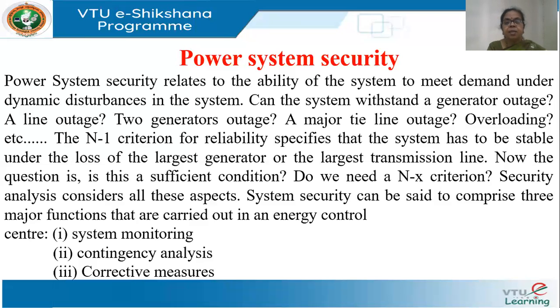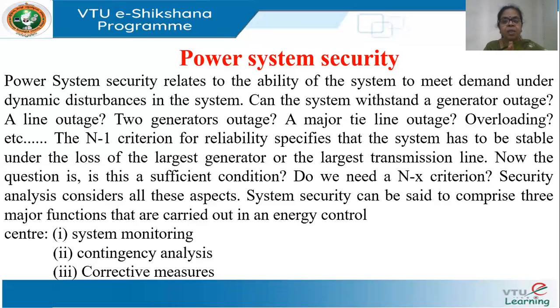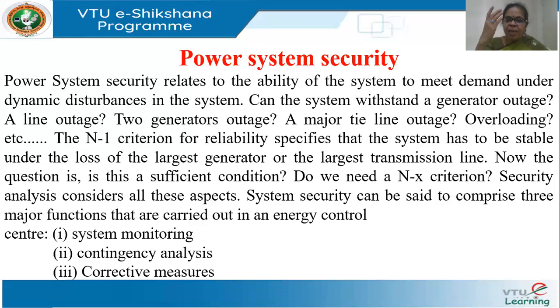The second function is contingency analysis. In my present state, how secure am I? What are all the faults that can occur, and can I ride through those faults? Is my system robust enough to withstand them? That is the analysis part. The third is corrective measures — if the fault occurs, what do I do? I keep the action plan ready: Plan A, Plan B, Plan C. If Plan A cannot be executed, go to Plan B. We must have all those corrective measures in place.